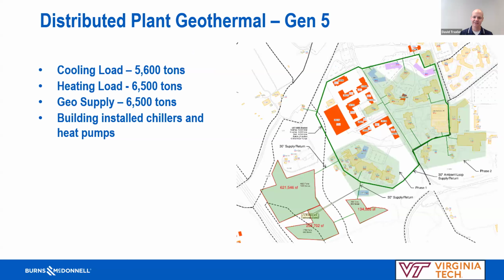It's the life science and veterinary district. Here, most of the buildings have building level equipment in them. And so it made a lot of sense, and plus the buildings are spread further apart, to do an ambient loop network. The piping is much more affordable. It's one plastic pipe instead of four metal pipes with insulation. And so here we had about 5,600 tons of cooling, 6,500 tons of heating. So we sized the bore field for the total load of 6,500 tons, and we had building installed chillers and boilers, or chillers and heat pumps in our analysis.